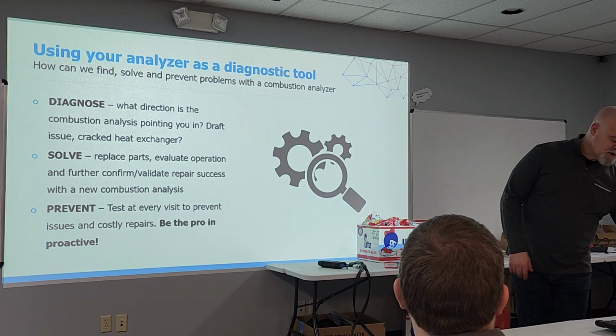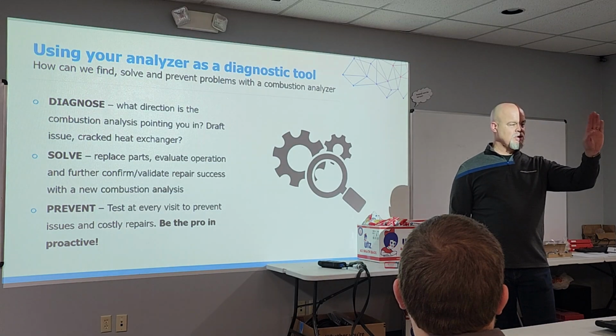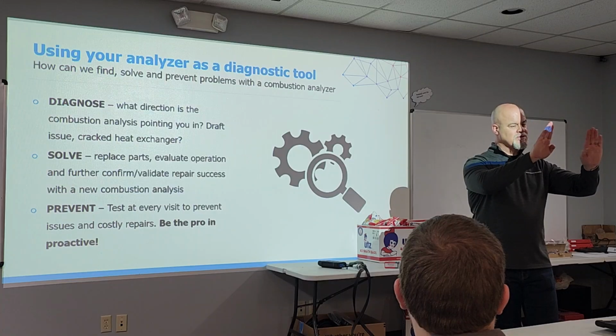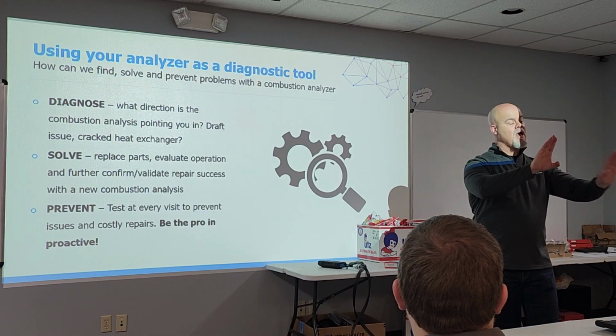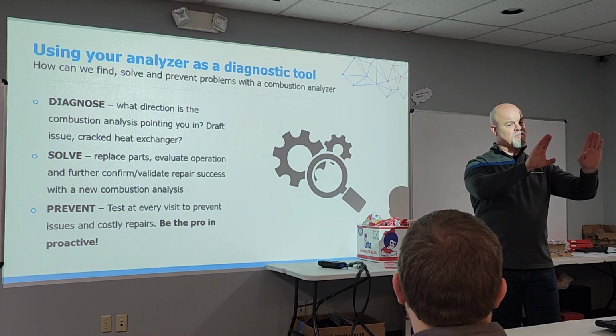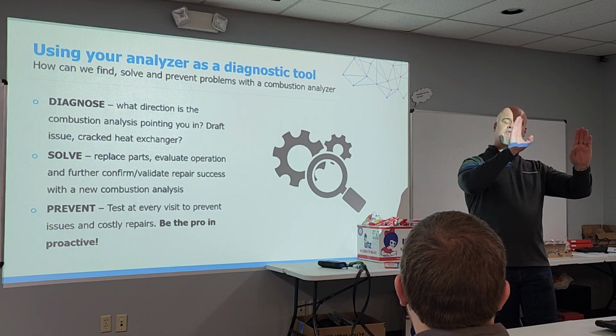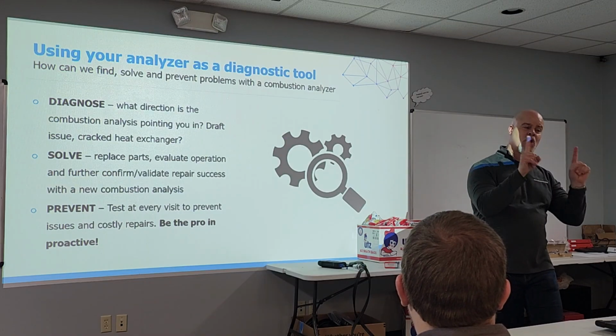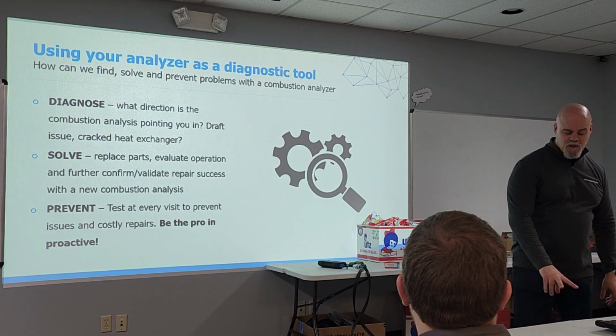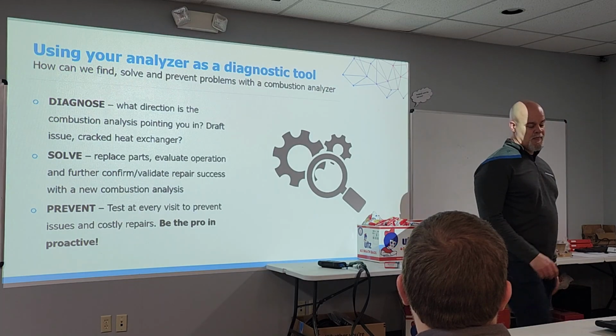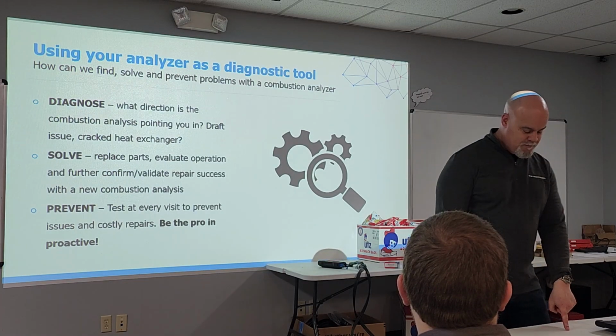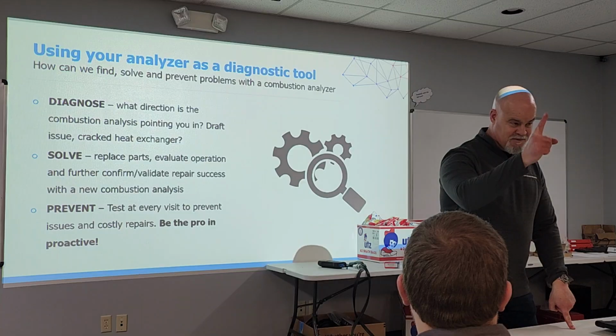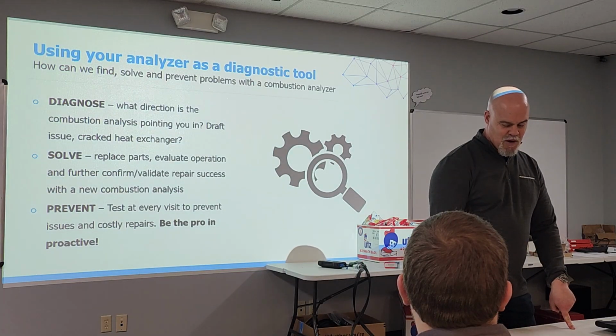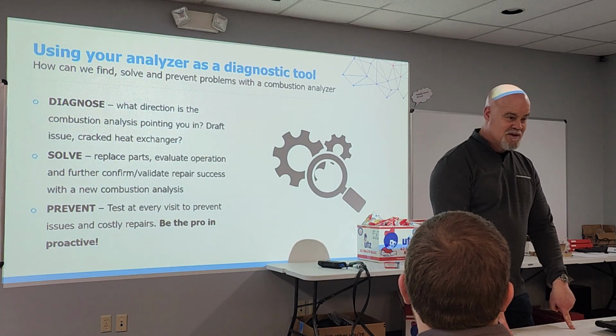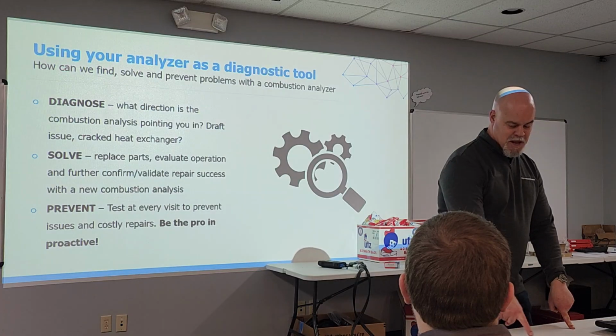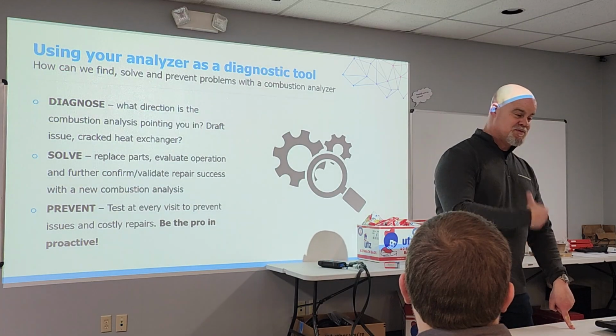Why? Because you have your baseline numbers that were askew over here. You now have your new set of numbers that should confirm that the adjustment or the repair that you made was the correct call. So now the numbers should be in line, and you're going to show your customer that. Don't just go, look, I fixed it, and run. No, you're gonna show them the before, you're gonna show them the after. And if you're really good, you're gonna take a screenshot of what the industry says your system should be running at.